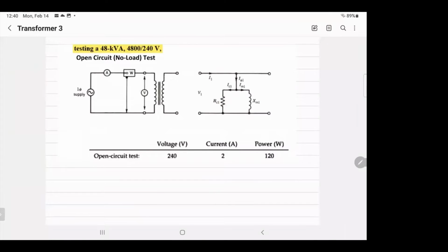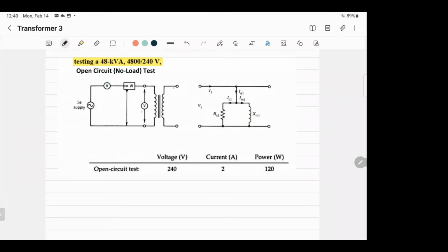Well, let's take just numerical values. That's a test we did on a 48 kilovolt-amp transformer, 4800/240 volt. So we are going to make the open circuit test here on this side, and on this side we are going to put the measuring instruments. And then usually you will find a table. Open circuit test: voltage is 240, current is 2 amp, power is 120. These are the measurements of the wattmeter, voltmeter, and ammeter, and that's exactly what we're going to do tomorrow in the lab.